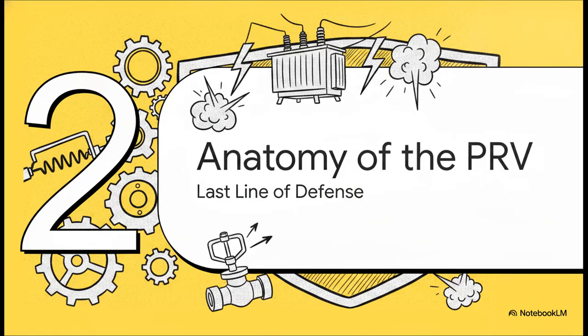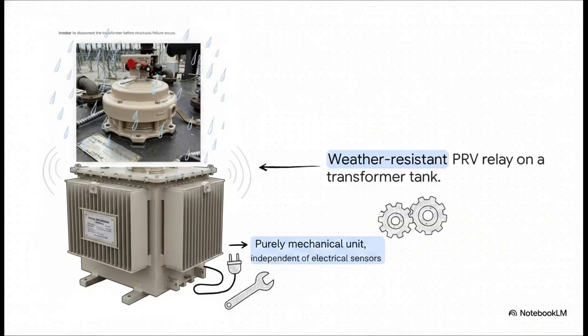Which brings us to part two, anatomy of the PRV, our purely mechanical last line of defense. Enter the transformer pressure relief valve, or PRV relay, our simple, incredibly fast hero. When you actually look at this device out in the field, it's remarkably unassuming. It's just a weather-resistant stainless steel or aluminum enclosure mounted right on top of the transformer tank.